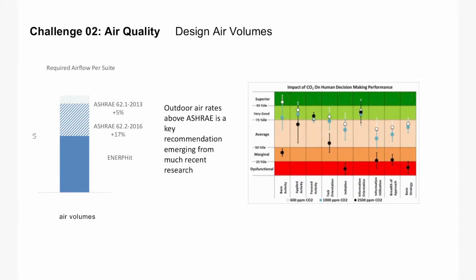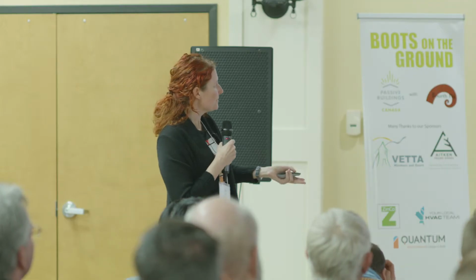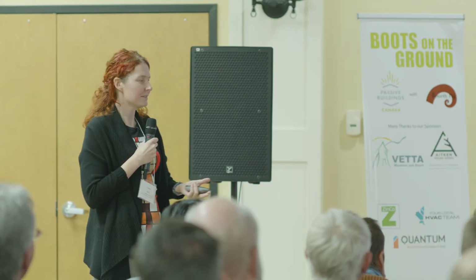Another challenge at this multi-unit residential level compared to the individual housing level is that when we followed the ASHRAE 62.2 2016 code, which is the requirement in Part 3, we found we had 17% more required ventilation than the passive house calculations from our passive house consultant. From an energy perspective, that was interesting. Looking at ASHRAE 62.1, the other option, we were 5% above that even.